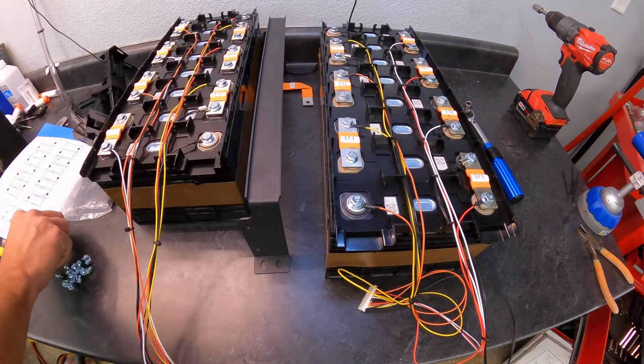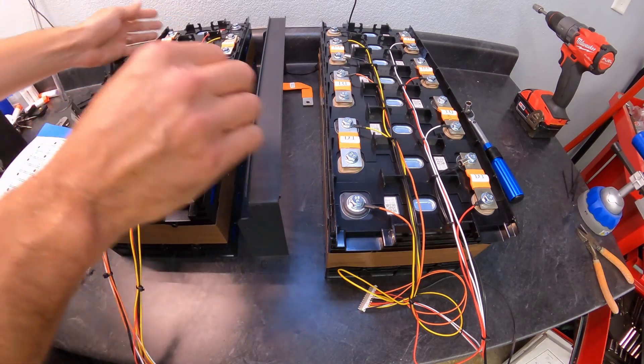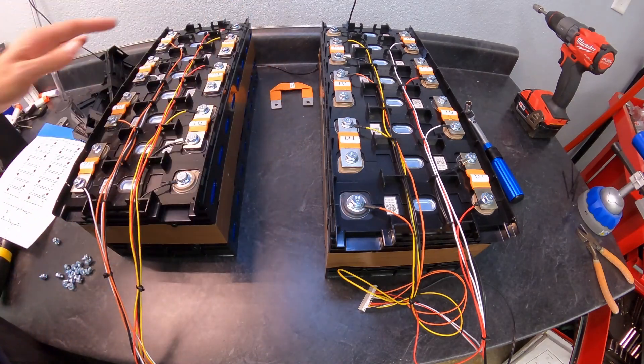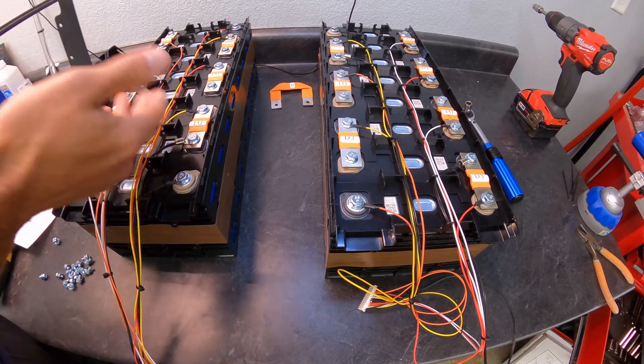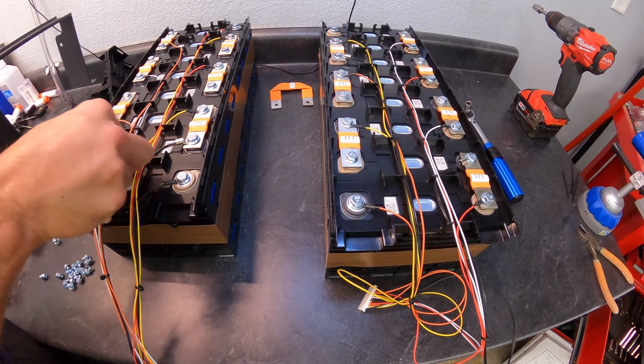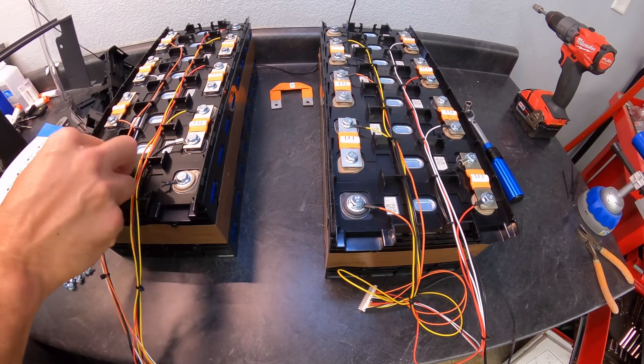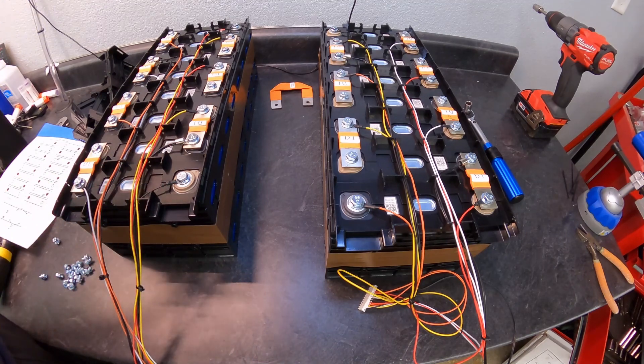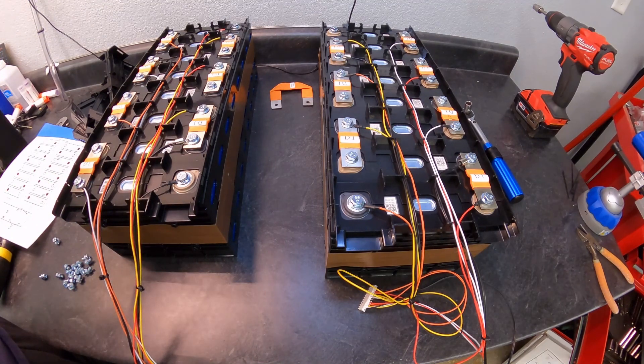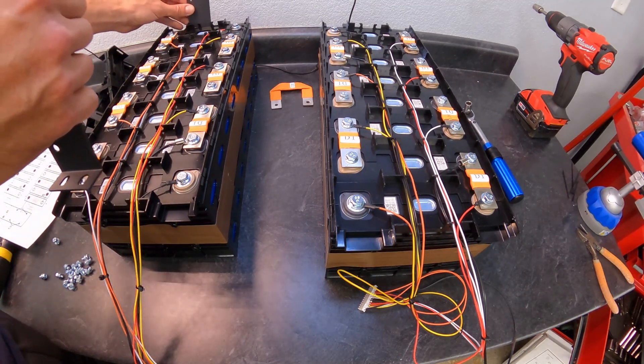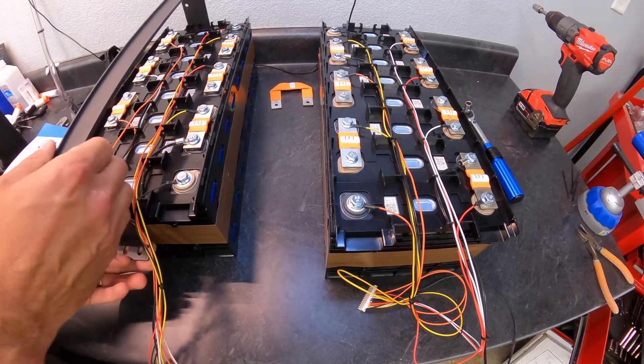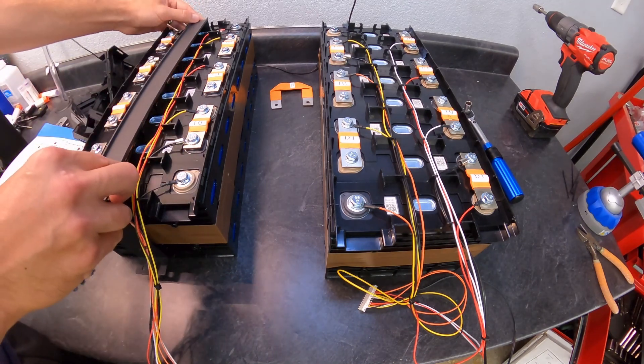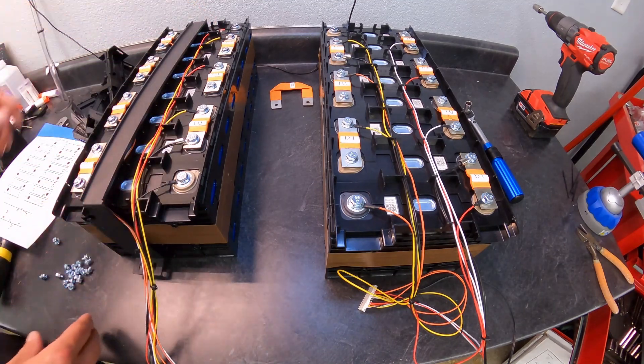It goes without saying that as we're doing this, we want to be mindful. This is powder coated steel and it's going to go over the top here in the middle. We want to make sure that our BMS wires are all in their little troughs just to be sure that we're not going to pinch anything, and also probably equally if not more important, make sure you don't short out on any terminals here. So I'm just going to pay a little extra attention as I'm going down. As you can see, that just goes over the top in the center part here.